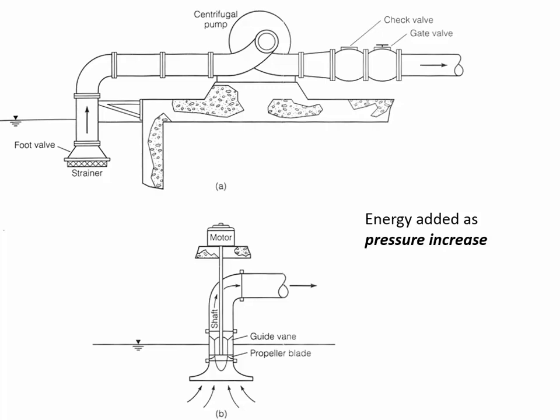So any questions so far about what this pump is doing or how it works? All right. One other thing to point out, you'll notice that they have a check valve here. The purpose of that check valve is to make it easier to start the pump after it's been off. It's not easy to start a pump if it's full of air. You can hope, and some pumps are pretty good about getting primed without being filled with water. But if it's just full of air and you turn it on, those impellers are spinning around inside of the pump, but they're designed to accelerate liquids, not to accelerate a gas. And so some pumps aren't very effective at creating the vacuum required to suck the water up into the suction side pipe and to fill the pump.